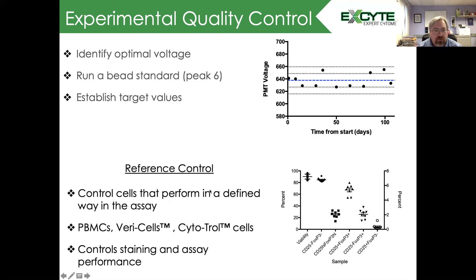In addition to that, you can run reference controls. Reference controls are cells that perform in a defined way in your assay. This can include frozen PBMCs. This can include the Veri-Cells. These are lyophilized cells from BioLegend. Or the Cytotrol cells, which are from Beckman Coulter. Or any other control that you feel will reproduce the quality data, both performing how the staining works and how the assay performs. And here's an example of that type of data where we're looking at a wide variety of metrics establishing a range that we would expect performance on these systems.